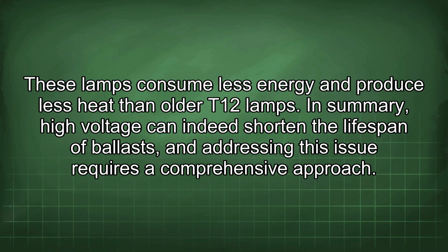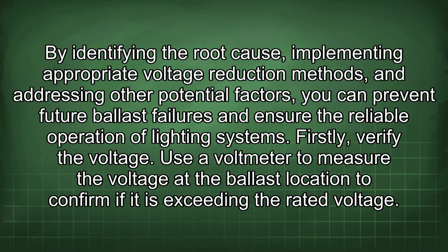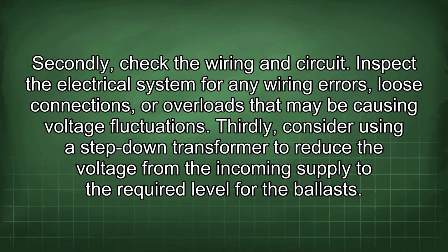In summary, high voltage can indeed shorten the lifespan of ballasts, and addressing this issue requires a comprehensive approach. By identifying the root cause, implementing appropriate voltage reduction methods, and addressing other potential factors, you can prevent future ballast failures and ensure the reliable operation of lighting systems. Firstly, verify the voltage. Use a voltmeter to measure the voltage at the ballast location to confirm if it is exceeding the rated voltage. Secondly, check the wiring and circuit. Inspect the electrical system for any wiring errors, loose connections, or overloads that may be causing voltage fluctuations.